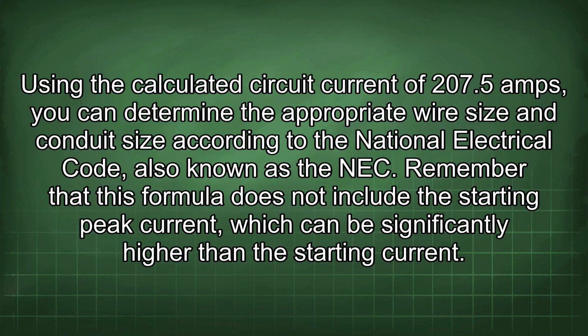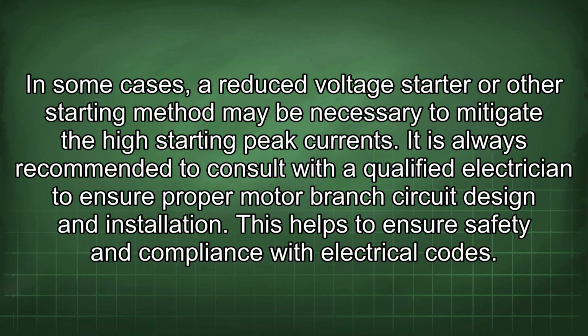Remember that this formula does not include the starting peak current, which can be significantly higher than the starting current. In some cases, a reduced voltage starter or other starting method may be necessary to mitigate the high starting peak currents. It is always recommended to consult with a qualified electrician to ensure proper motor branch circuit design and installation. This helps to ensure safety and compliance with electrical codes.